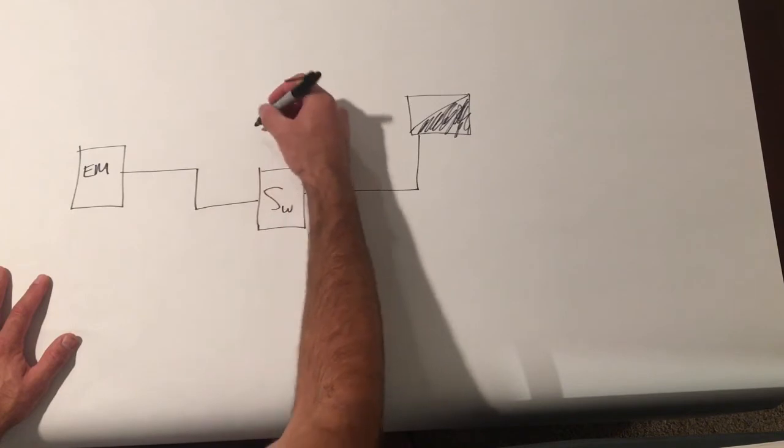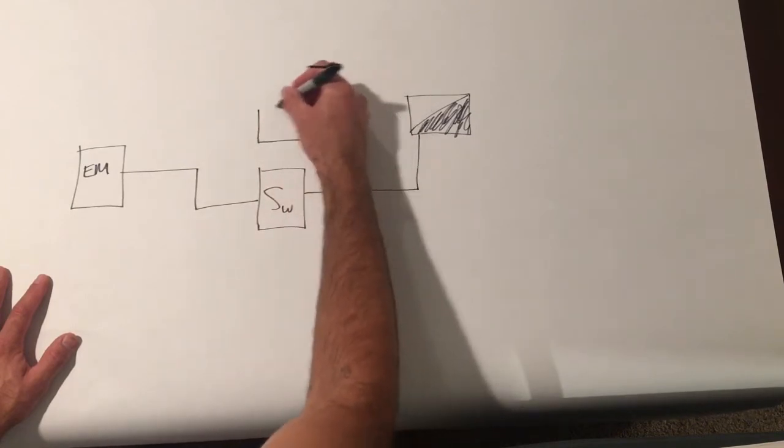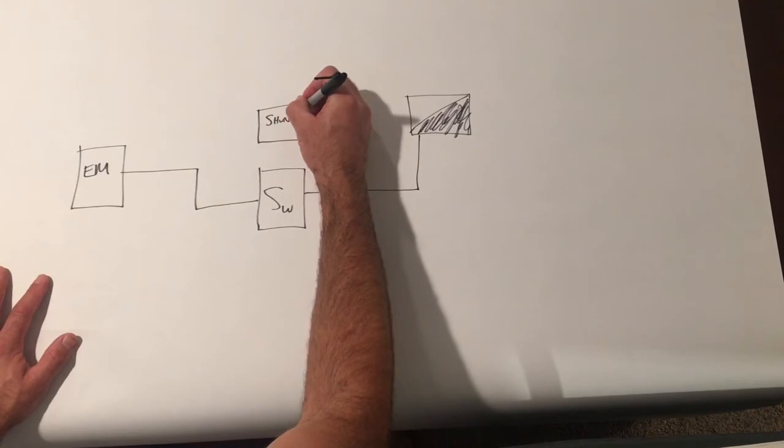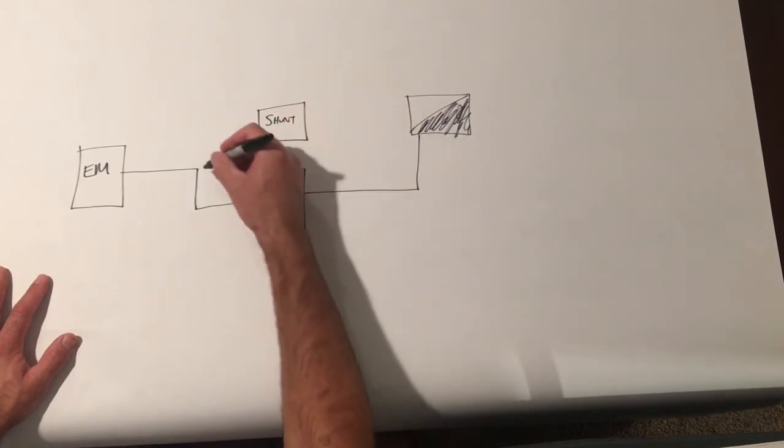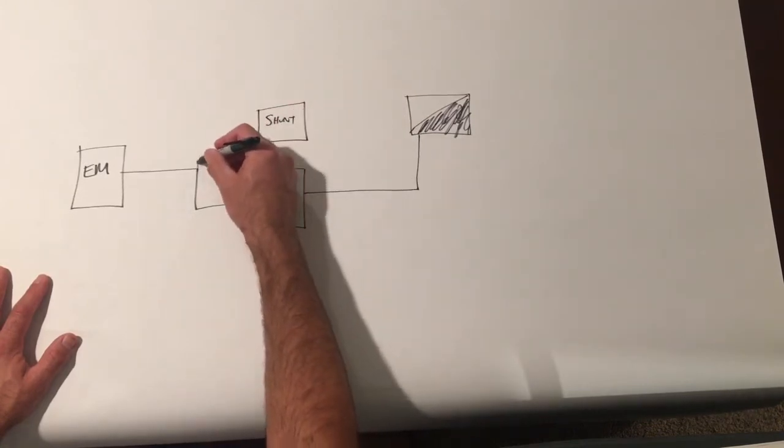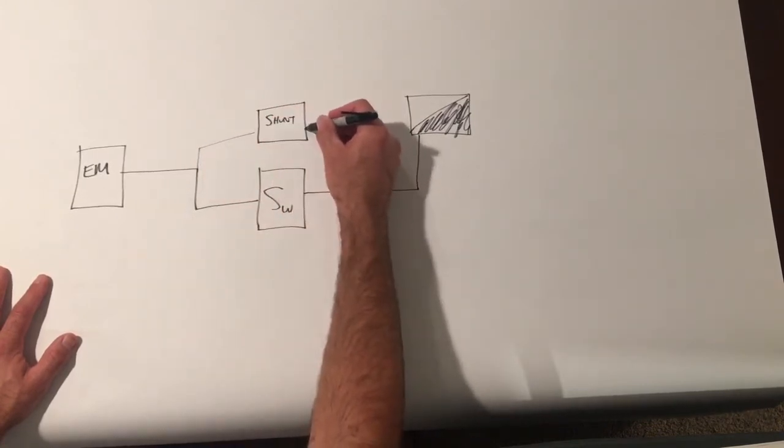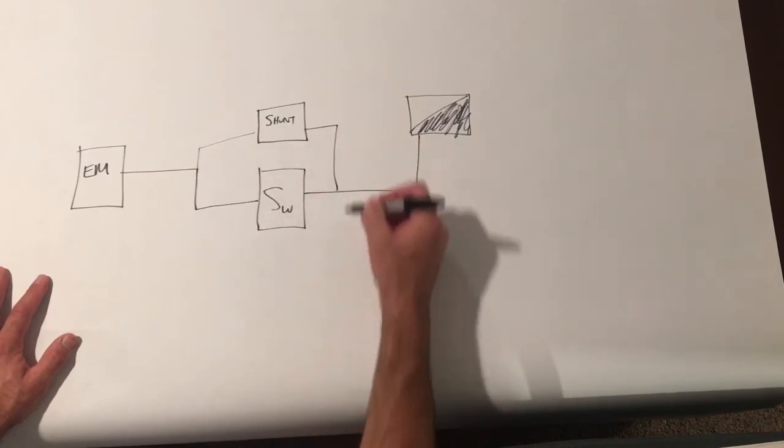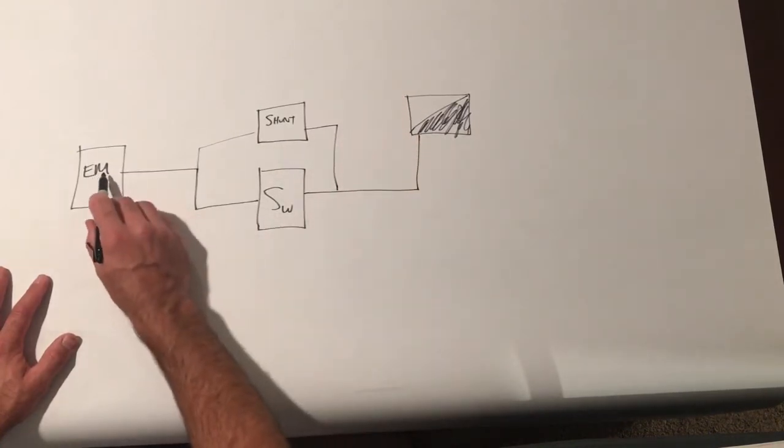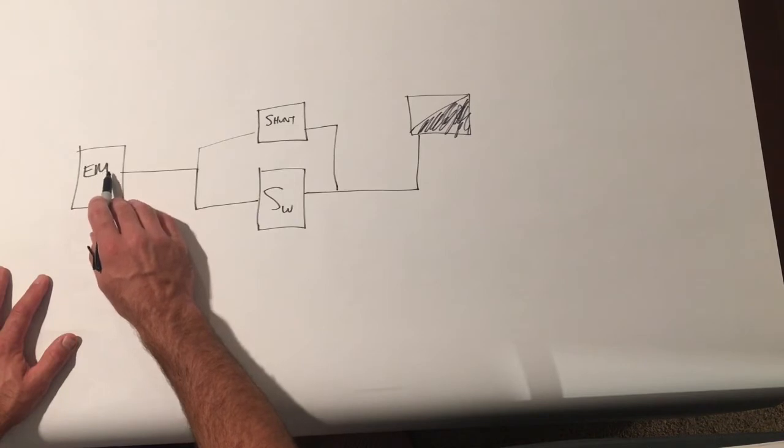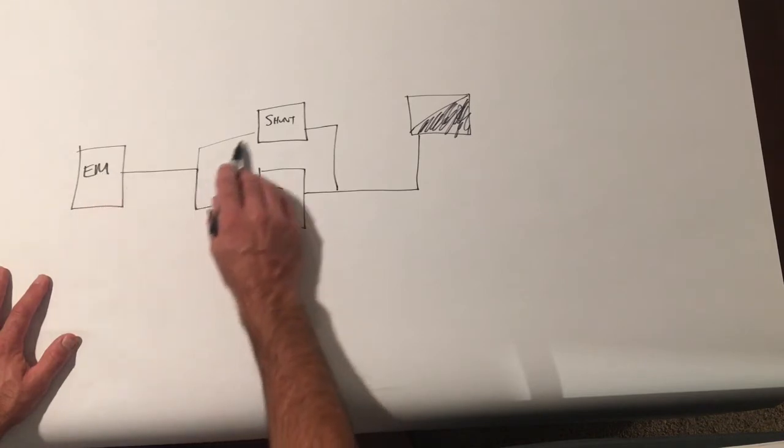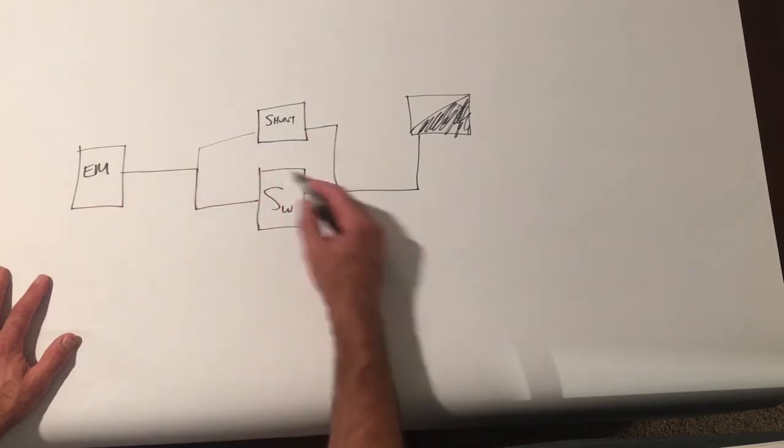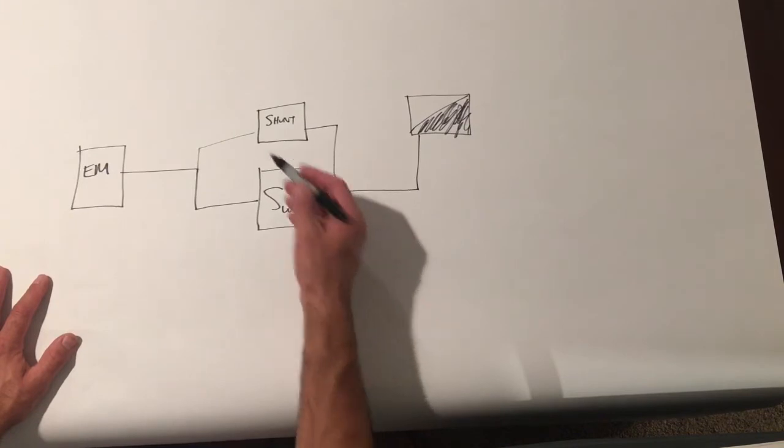So to make this work, we're going to introduce a device. I'm going to show it right here, which is a shunt relay. We're going to wire that in parallel with our switch. And the idea is when power is lost, the shunt relay closes, turns the light on regardless of the switch position.